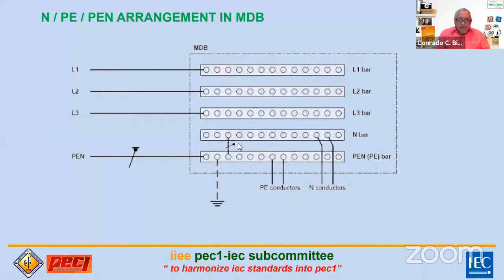That's the priority. If you look here, there's a connection between the two, this is the PEN bar. It connects there. Then your neutral, all your neutral conductors connect here, and all your protective earth conductors connect to this PEN bar. It's very important to follow how this is done in our switchboards or main distribution boards, how the bus bars, earthing bar, and neutral bar are physically arranged and connected.